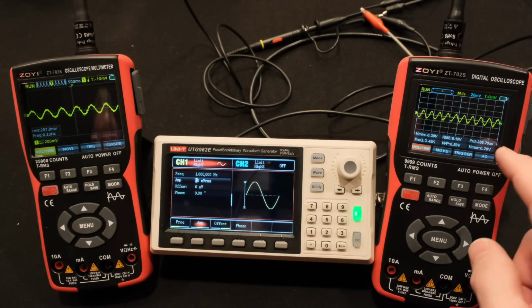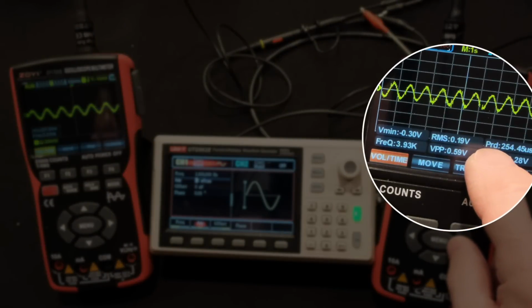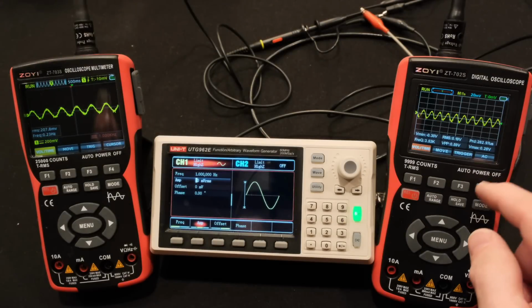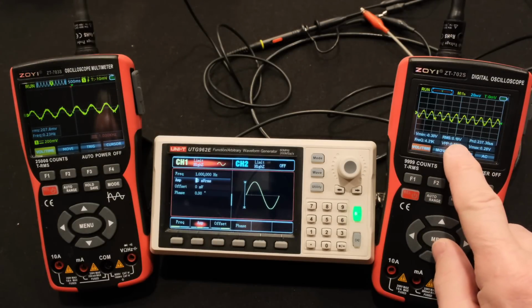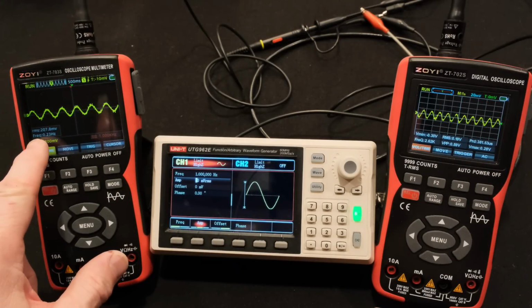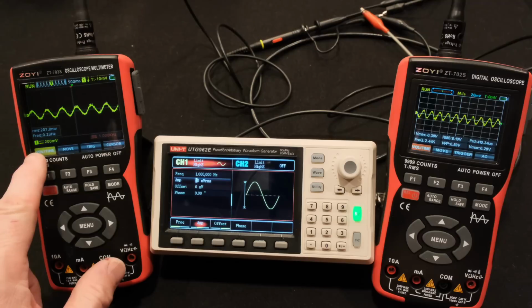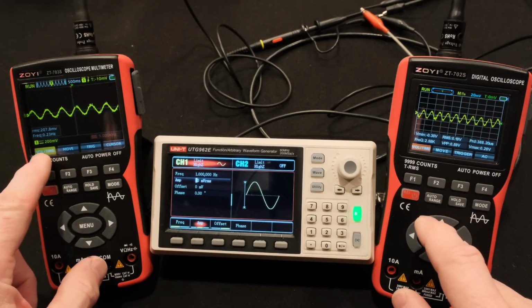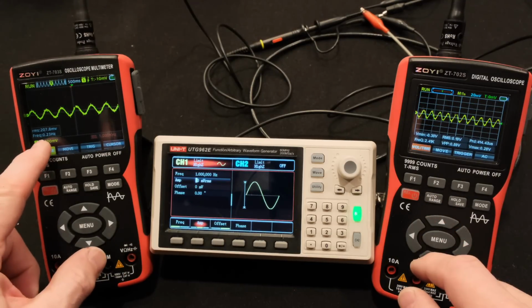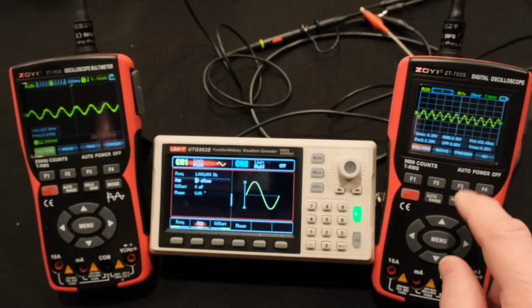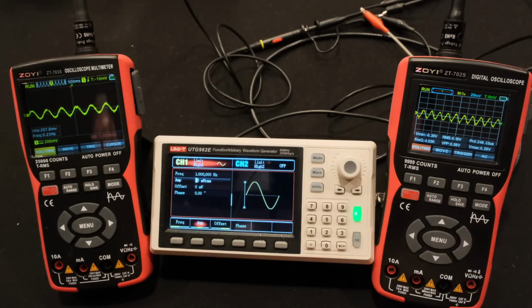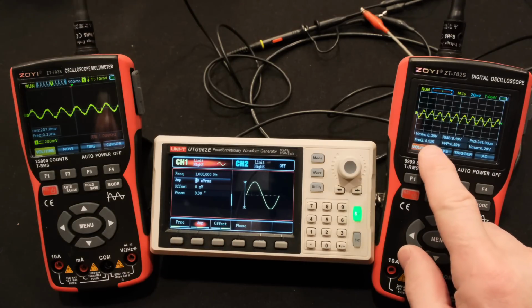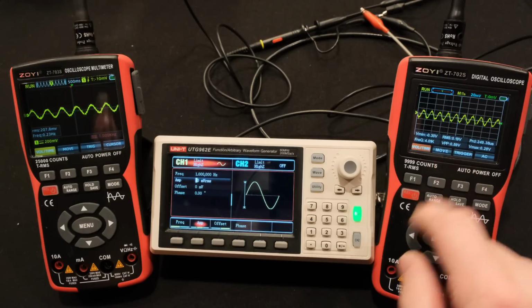So over here, same kind of thing. Its RMS is 0.19, so it thinks it's 190 millivolts. And you notice it's 0.19, and over here you got 207.8 millivolts. So if you notice as we go through this, if you can see this reading, it's just a better reading, 207.8 millivolts versus 0.19. Okay, and 0.23 hertz, and over here it's 2.8K, so that's way off.